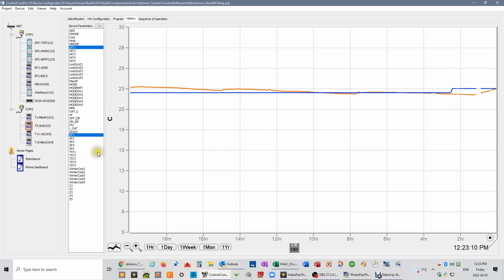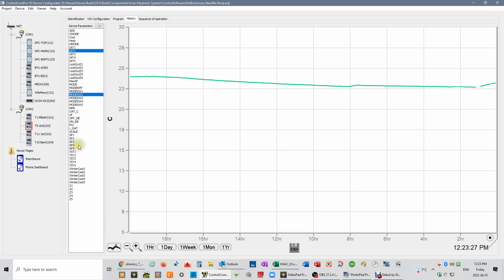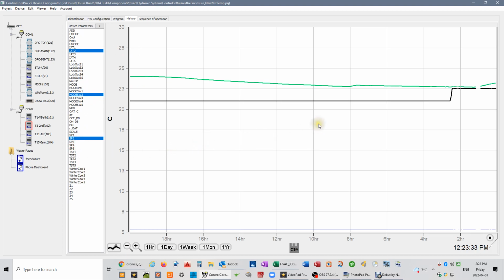The actuator was open. And if we want to add in the actuator control, we can see what the actuator's been doing. So it was off. And now it's been on since 4:08 a.m. this morning. And we can do the same thing with any of the zones. Oops, got the wrong zone there. So we can see that with this one, the actuator has been off the entire time. And no matter what my set point is, it's actually been warmer than this the whole time.